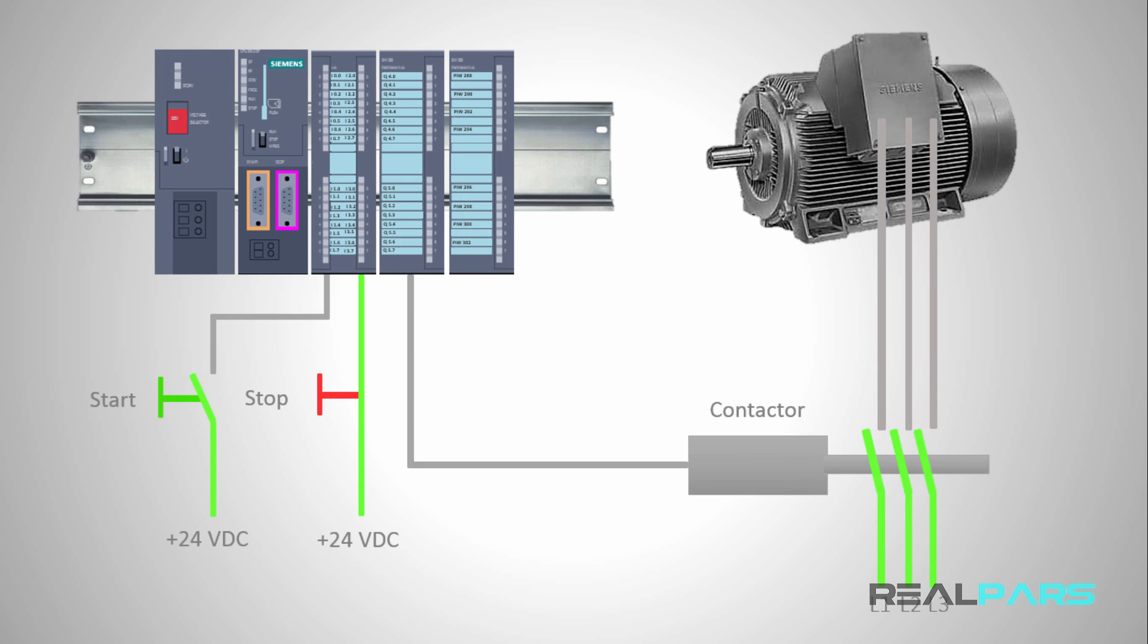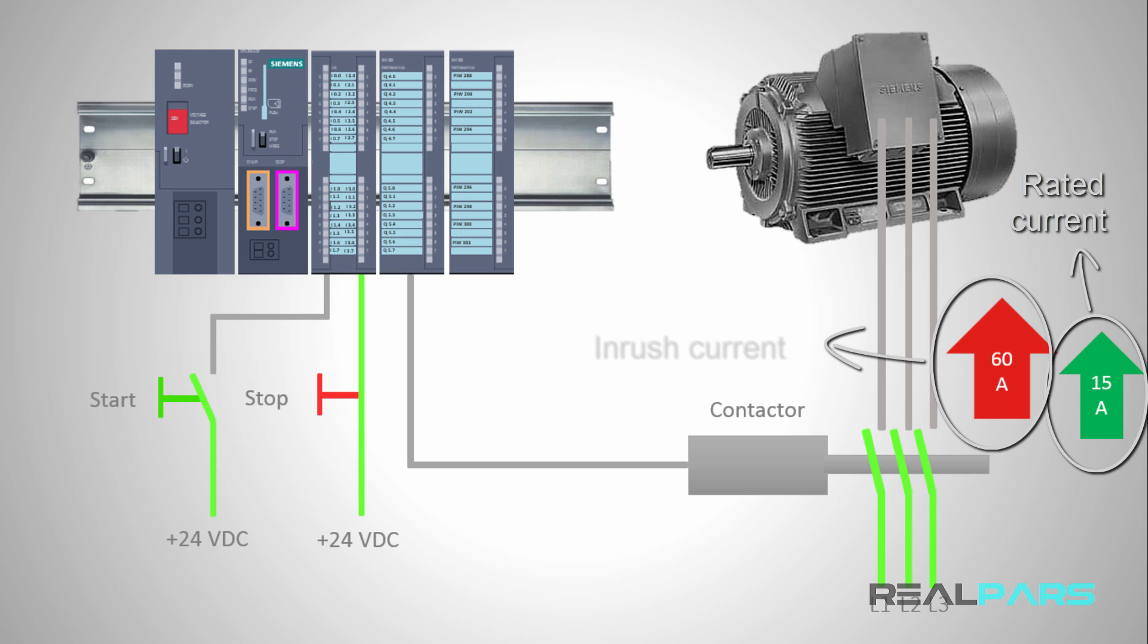When you start a large electrical motor, in the first few seconds that the motor is starting, it will draw much more current than the rated current. This is called the inrush, or start current. For instance, if you have an electrical motor that draws 15A during normal running operation, at the moment of starting the motor, this current can increase up to 60A, that's 4 times greater than the rated current.